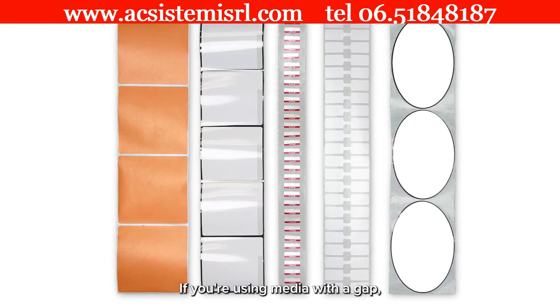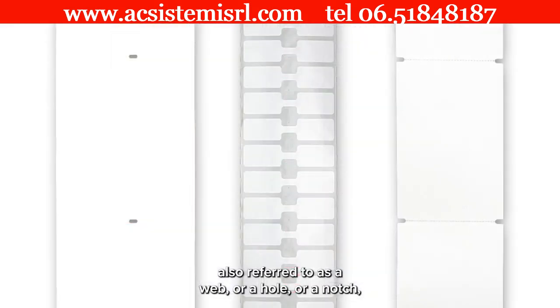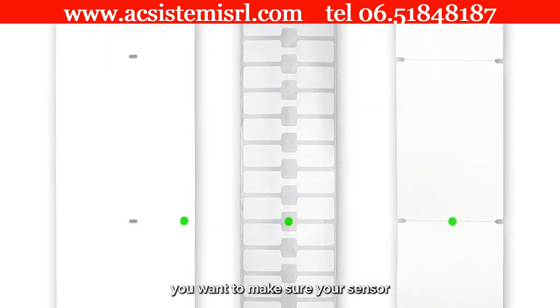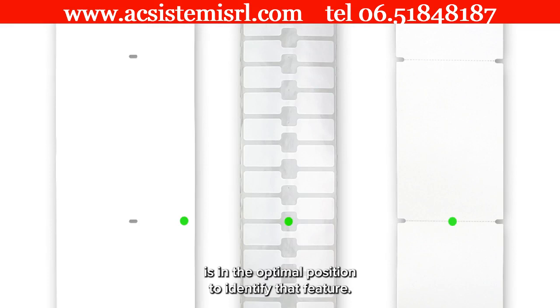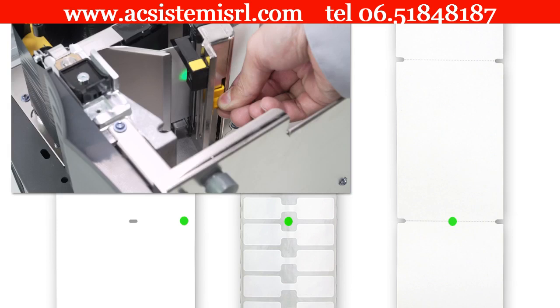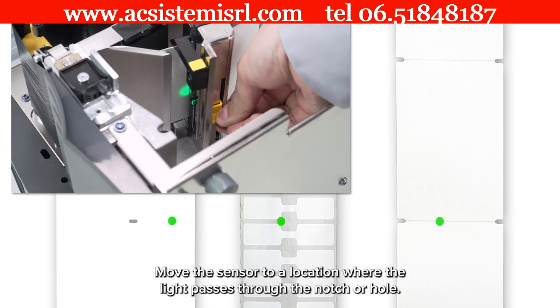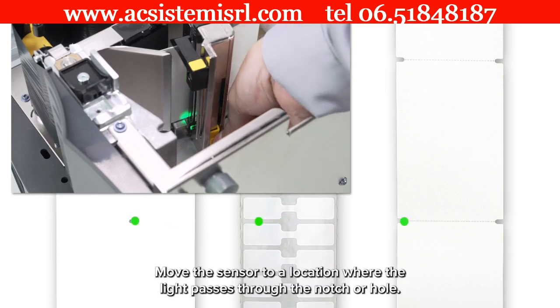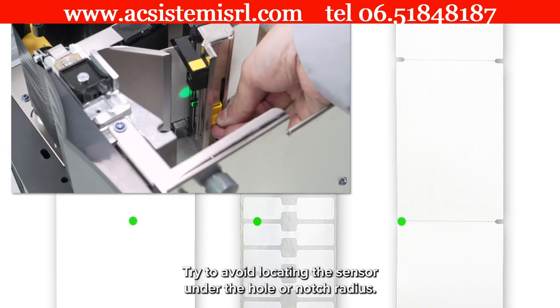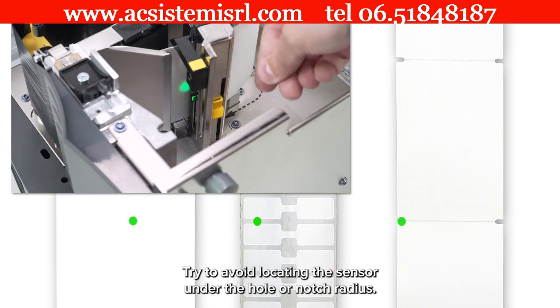If you're using media with a gap, also referred to as a web, or a hole or a notch, make sure your sensor is in the optimal position to identify that feature. Move the sensor to a location where the light passes through the notch or hole, and try to avoid locating the sensor under the hole or notch radius.